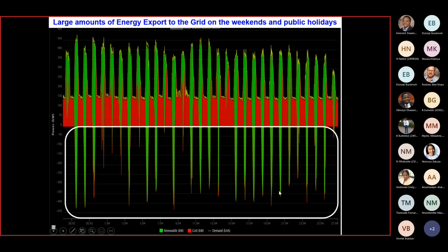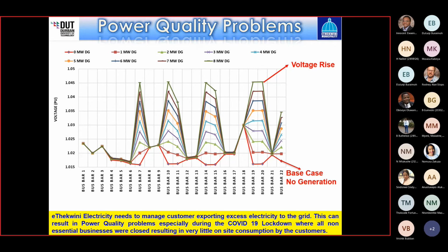The problem comes on weekends, when companies are closed. On weekends, public holidays, election days, and December holidays, they tend to export bulk electricity to the grid. If everyone does that, you don't have adequate load, leading to problems such as voltage rise. In studies for another project, we saw that as you increase the generation fed into the network during periods of lower load, voltages on the network rise and can exceed limits, causing problems.